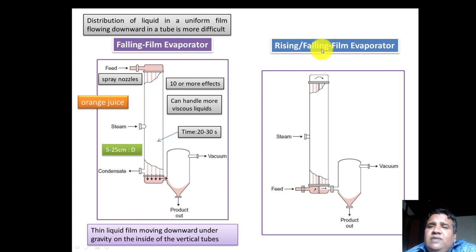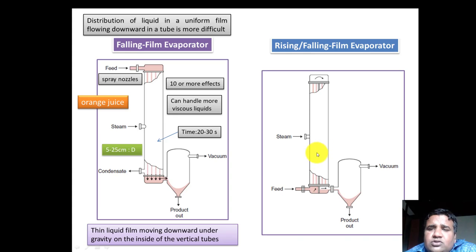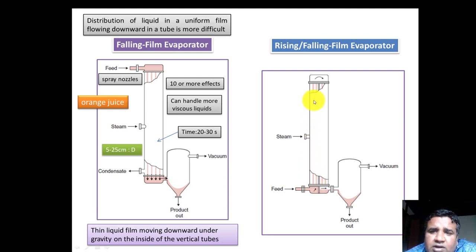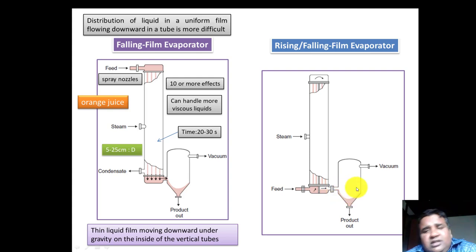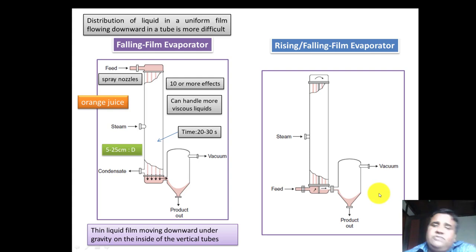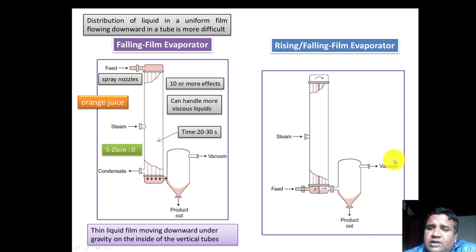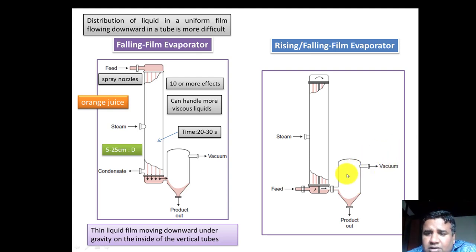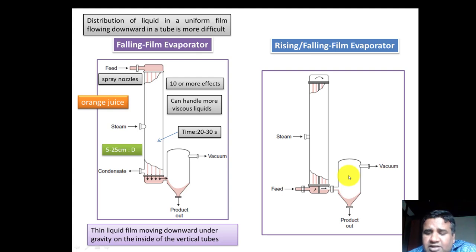There is also a combination of rising and falling film evaporators. In one section, tubes are arranged in a cylindrical form. Outside the tubes there is steam circulation. Half of it is the rising film evaporator — material rises to the top — and after reaching the top it comes back down. In this way we can concentrate it better. It is followed by separators where the concentrated product is collected, and vapors are subjected to further compression and vacuum is created to increase the yield of vapor.